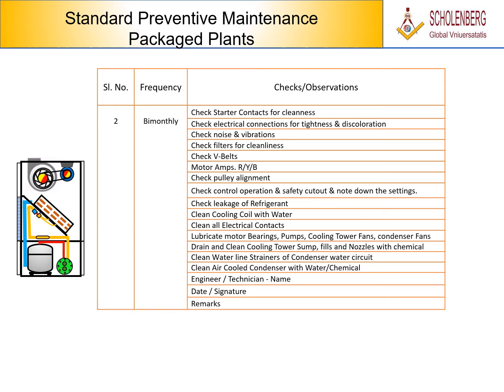2. Bi-monthly. Check electrical connections for tightness and discoloration. Check noise and vibrations. Check filters for cleanliness. Check V-belts. Motor amps, R, Y, B. Check pulley alignment. Check control operation and safety cutout and note down the settings. Check leakage of refrigerant. Clean cooling coil with water. Clean all electrical contacts. Lubricate motor bearings, pumps, cooling tower fans, condenser fans. Drain and clean cooling tower sump, fills and nozzles with chemical. Clean water line strainers of condenser water circuit. Clean air-cooled condenser with water, chemical. Engineer, technician, name, date, signature. Remarks.